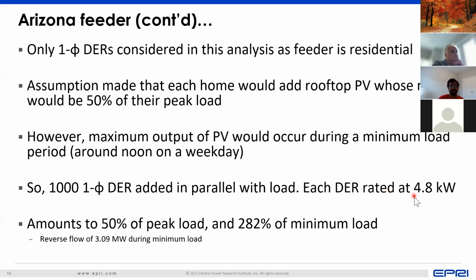So when we take into consideration the amount of PV, the rating that we have, we see that the total DER will amount to 50% of peak load, but it actually amounts to 282% of minimum load, which means that if every house puts a 50% rating PV panel during a minimum load period, there could be a reverse flow of 182%, because it's 282% of the load. There could be a reverse flow of 182%, which in this case was around 3 megawatts, back into the transmission network. And that is something which is very important for transmission planners to consider, because now if this occurs at every feeder, at every substation, it means it will change the way in which we operate the transmission system.